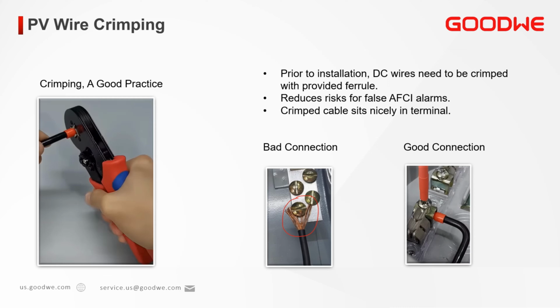Now I want to highlight the importance of using the DC and AC wire terminals included in the box with the inverter. Over the years, we have learned that a number of the nuisance AFCIs have been due to improper installation of the PV wire to the inverter PV input terminal. Please make sure to crimp the wire and to use the wire terminals. The wire terminals should be properly crimped based on the size wire. We recommend a 12 gauge copper for the PV connection.